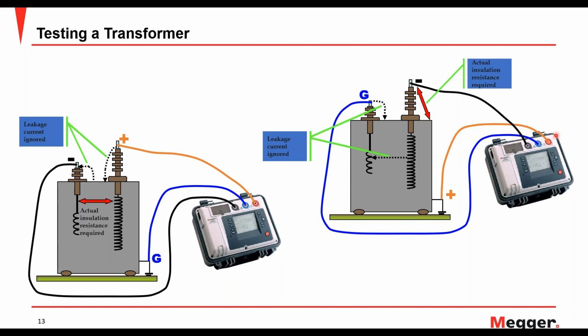Similarly, if I want to do it the other way around, I want to measure between my high side and my ground, I would just hook up my negative to high side, positive to ground, and I don't care anything about the low side. So I'm just guarding it out of the measurement, and that's how you will know that you are specifically measuring only between high side and ground.